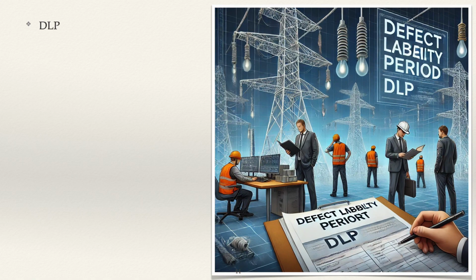M. Inspections during defect liability period. The purpose is to monitor the performance of the transmission line during the defect liability period and ensure that any issues that arise are addressed. The inspection focus on 1. Conducting regular inspections to identify any defects, such as conductor sagging, tower settlement, or hardware failure. 2. Ensuring that the contractor promptly rectifies any defects identified during the liability period, ensuring the long-term reliability of the transmission line. That brings us to the end of knowing about consultant engineers.